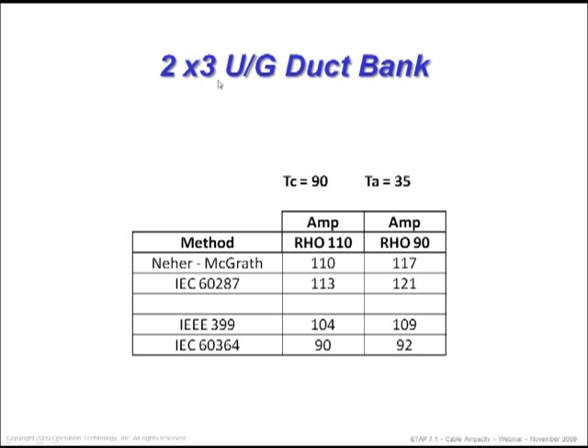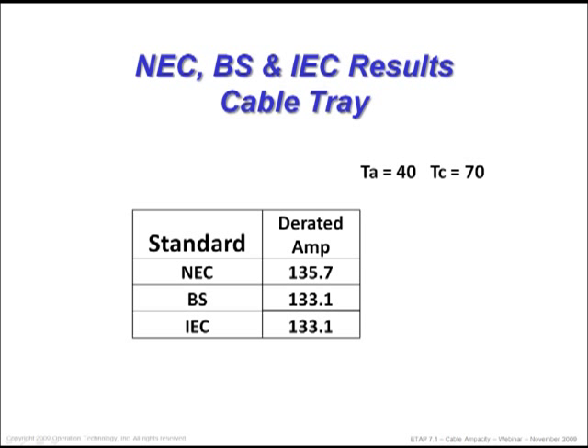This is a two-by-three duct bank. If you go to IEEE 399, the results are more conservative but still very close — IEEE 399 is closer to the thermal analysis, whereas IEC 60364 is a lot more conservative than IEEE 399. With that, I'm going to move to the next item: comparing NEC, BS, and IEC standards for cable trays.